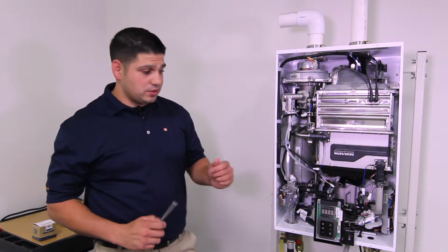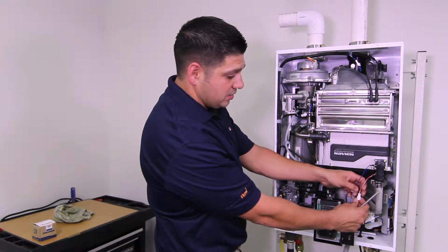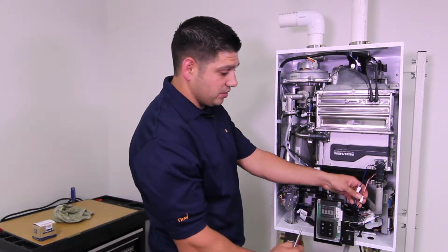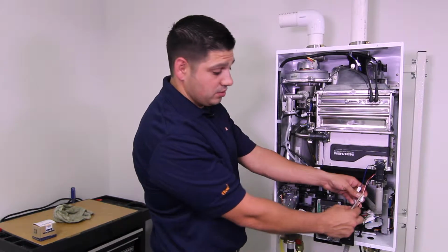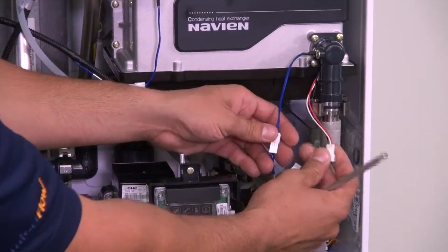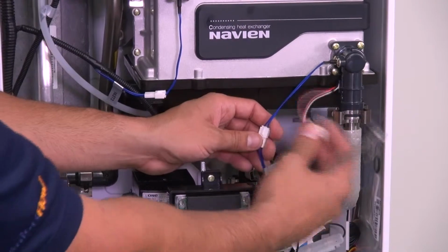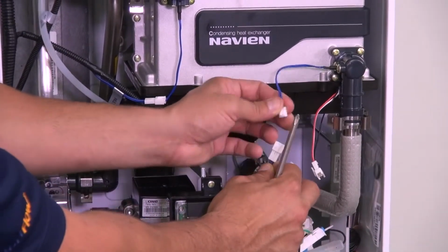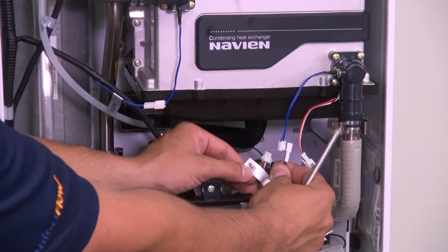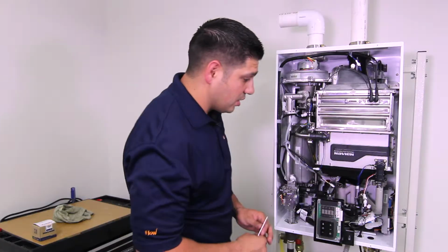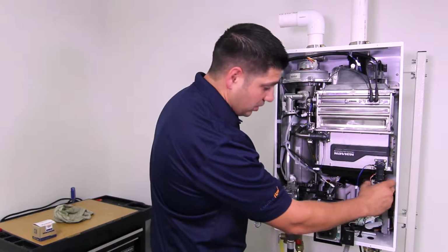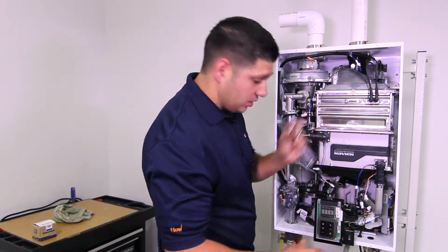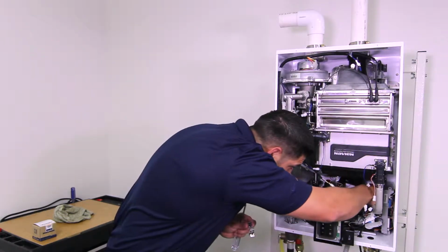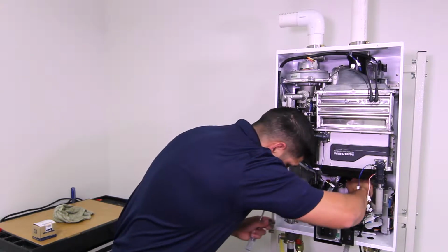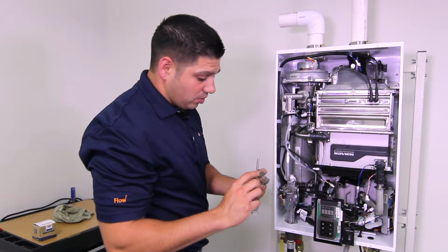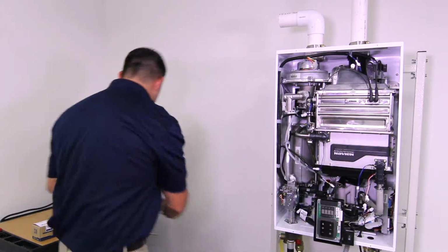So the first thing we're going to do in this process is disconnect your electrical. So you have 2 plugs going into this unit, and they are color coordinated, so you shouldn't have any problem reconnecting them. So you got your red, white, and black, which is your flow sensor, and you have your blue thermistor connection, and the wiring harness is labeled inlet on your thermistor. So once we got that removed, we're going to go ahead and pull off one 27 clip and your second 27 clip. So both your clips are marked 27. Make sure not to lose these.